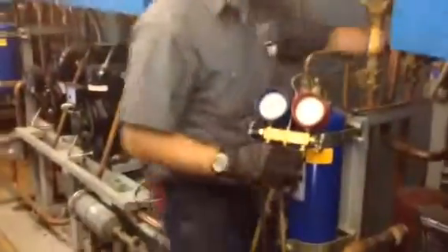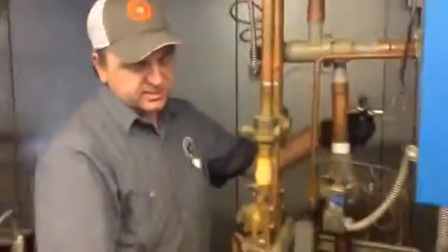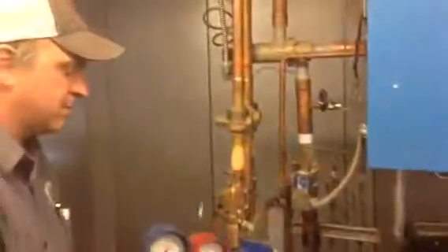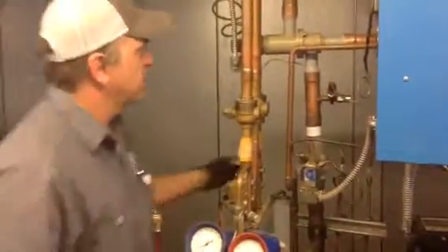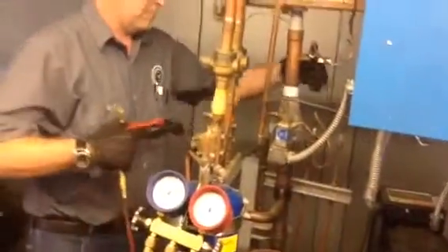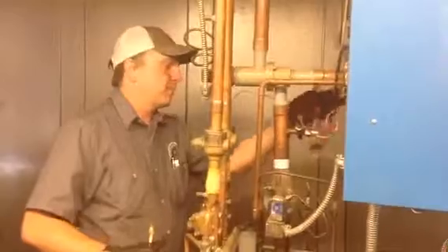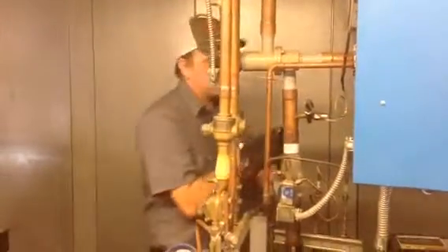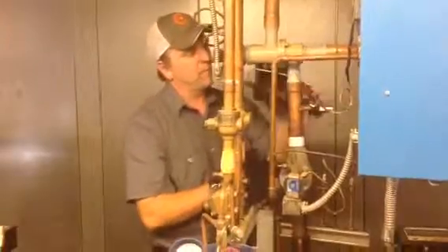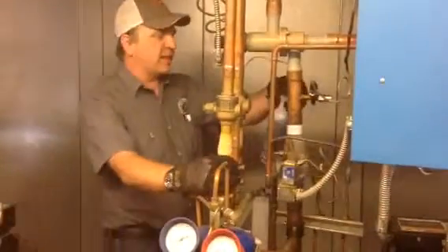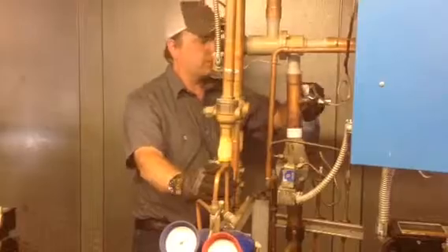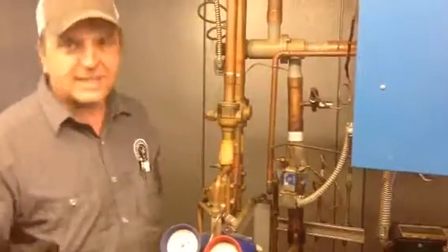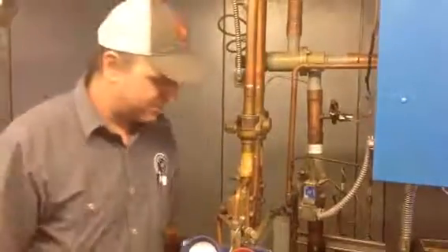Reverse your process. Remove your gauges. Put your cap back on. Then leak check what you did. It's always good, anytime you put gauges on a rack or you break something open, leak check. You don't want to leave a leak. No leaks. That's how you calibrate transducers. Have a good day.